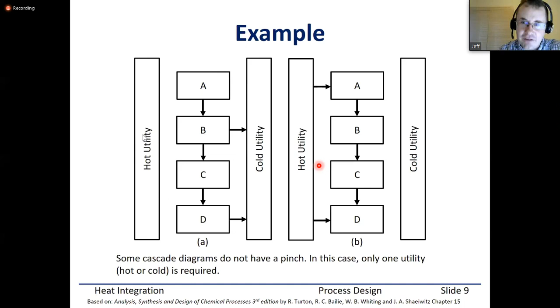The next step is to determine the minimum number of heat exchangers above the pinch. You should be aware this does not necessarily correspond to the final design of the heat exchanger network. We're just going to determine the minimum number of exchangers required above and below the pinch. After we identify the pinch temperature, we separate the problem into two parts. Since we know that we're not going to transfer heat across the pinch, we design the heat exchanger networks above and below the pinch separately. So we will start above the pinch at temperatures higher than the pinch temperature, and we will determine the minimum number of heat exchangers by trying to match hot streams with cold streams in a way that minimizes the number of heat exchangers.